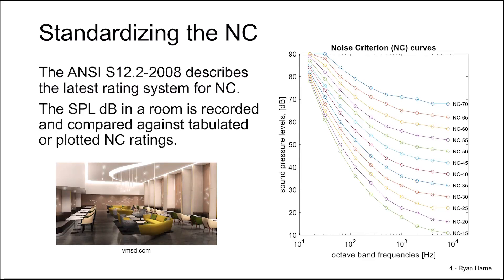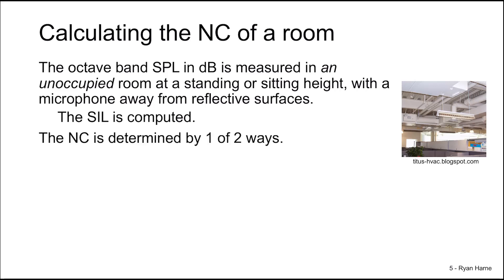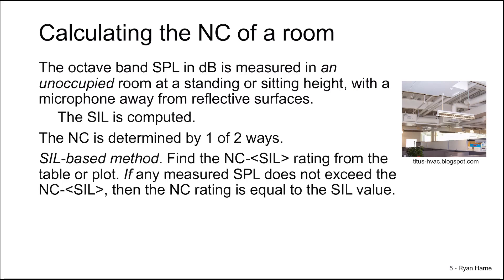We see the ratings as shown here on the right. We calculate the NC of a room by measuring the octave band SPLs in decibels. The room must be unoccupied, and the microphone should be placed away from reflective surfaces at around a sitting or standing height. The speech interference level is first computed. We then determine the NC of the room by one of two ways. First, we use the speech interference level method — we find the NC-SIL rating from the table or plot. If there are no measured SPL readings that exceed the NC-SIL rating, then the NC rating of the room is equal to the SIL value.